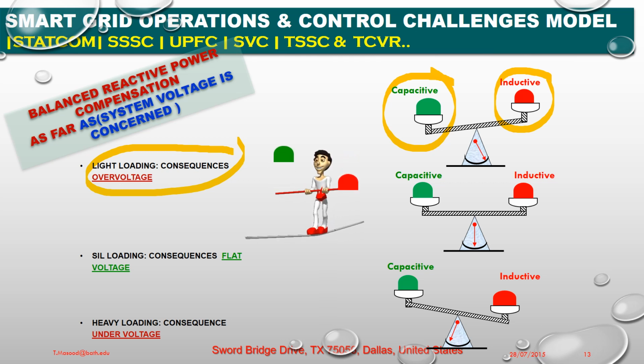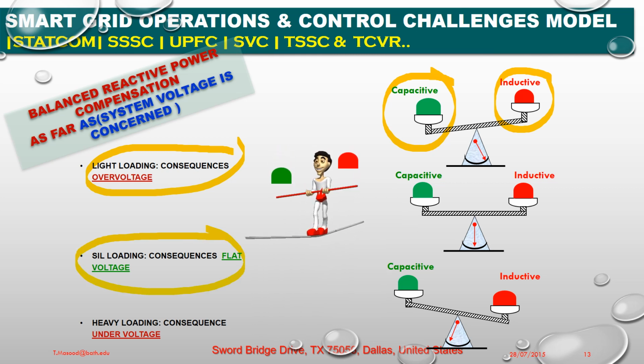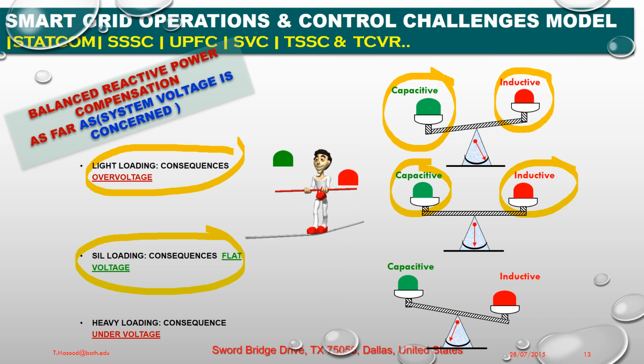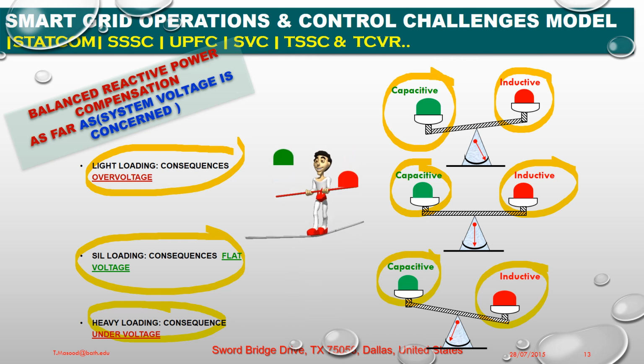Number 2, flat loading. The consequence of flat load is that capacitive and inductive are equal. Capacitive and inductive both are equal, balanced, which means flat load, flat voltage. Number 3, heavy loading. The consequence is under voltage, which means more inductive and less capacitive. So we need to have balanced reactive power in order to maintain the voltage level as required. That is important for us to understand.